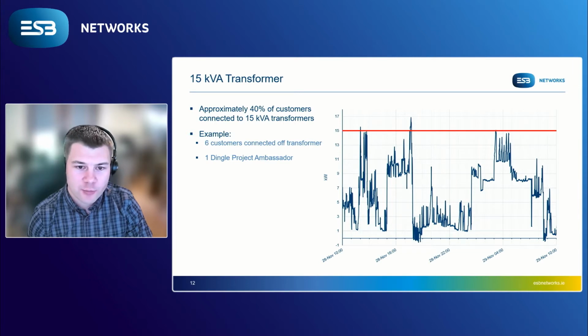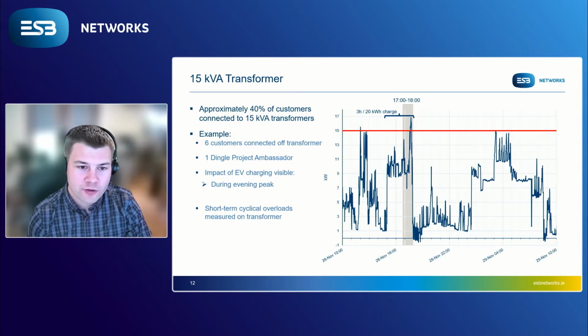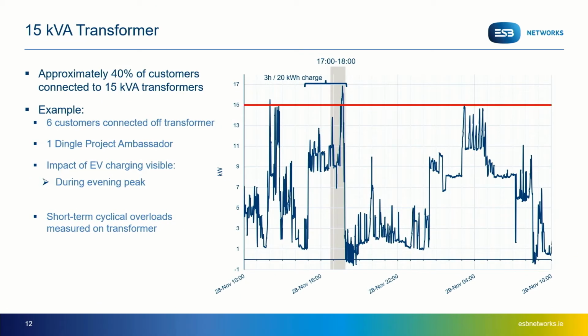In this particular example, there are 6 connected customers, including one of our Dingle ambassadors. We can see the large increases in power flow through the transformer between 3pm and 6pm, when a 3-hour charge was being completed. This happened to coincide with one of the traditional peaks in energy usage on the grid, and between 5 and 6pm, highlighted in the grey background, you can see a short-term overload measured on the transformer above the red line.